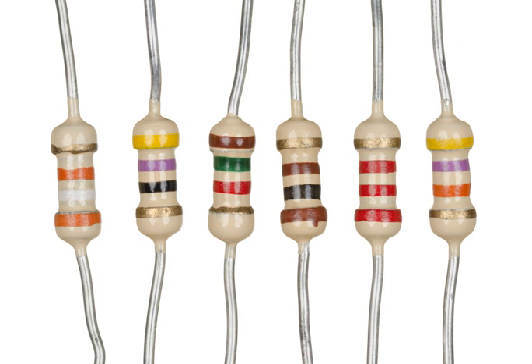Some laboratory-quality ohmmeters, especially milliohmmeters, and even some of the better digital multimeters sense using four input terminals for this purpose, which may be used with special test leads. Each of the two so-called Kelvin clips has a pair of jaws insulated from each other. One side of each clip applies the measuring current, while the other connections are only to sense the voltage drop. The resistance is again calculated using Ohm's law as the measured voltage divided by the applied current.